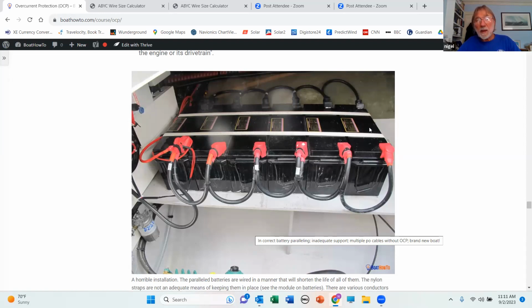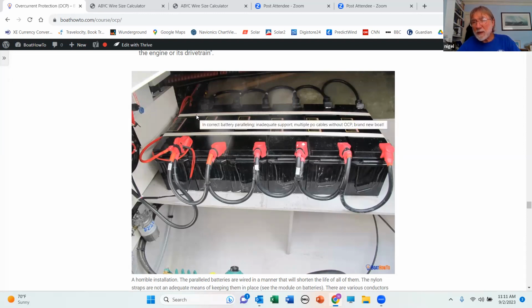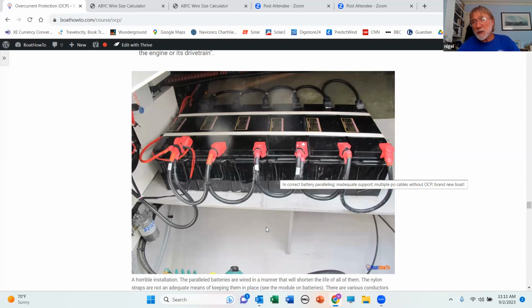So if you have parallel batteries, for years we've said, take one conductor, the negative off of one end and the positive off the other, so that you force the current through all of the batteries a bit more evenly. But nevertheless, you still get very uneven current distribution on charge and discharge cycles. What we need to do with these parallel installations is set up a bus bar, a metal bar, off the batteries, and come off of all of these batteries with the same length conductor. So the ones that are closest to the bus bar, you're going to have to snake the conductor around a bit because it'll be longer than it needs to be.